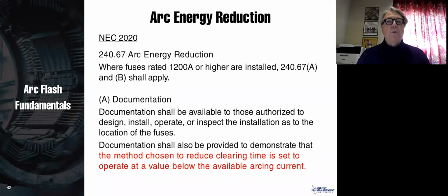NEC 2020 240.67, we have been talking about circuit breakers. What if you have a fuse? Then are there any requirements? Well, it turns out that there are. It says where fuses rated 1,200 amps or higher are installed, these things below shall apply. Number 1, you have to have documentation, and it says documentation shall also be provided to demonstrate that the method chosen to reduce clearing time is set to operate at a value below the available arcing current. Whoa, this made things a lot more difficult for design engineers, because they're saying when you select a fuse 1,200 amps or higher, you need to verify that it is going to operate below the arcing current of the system. So, there you go.